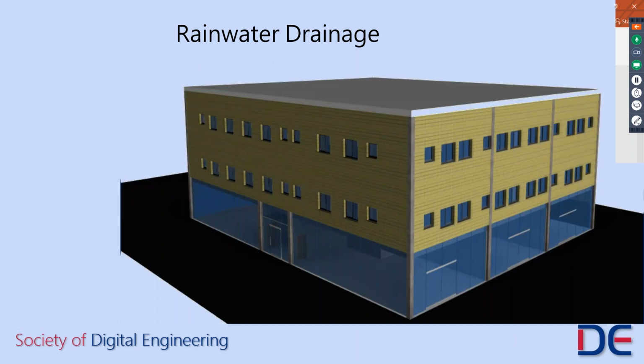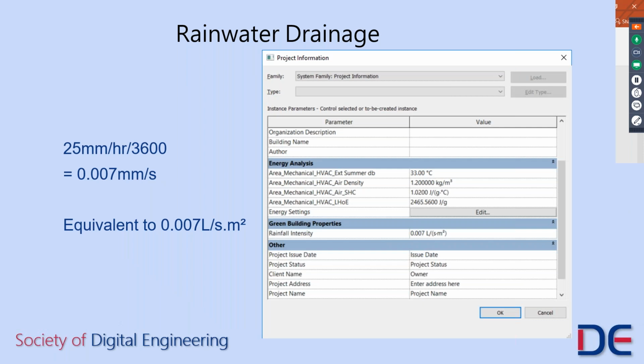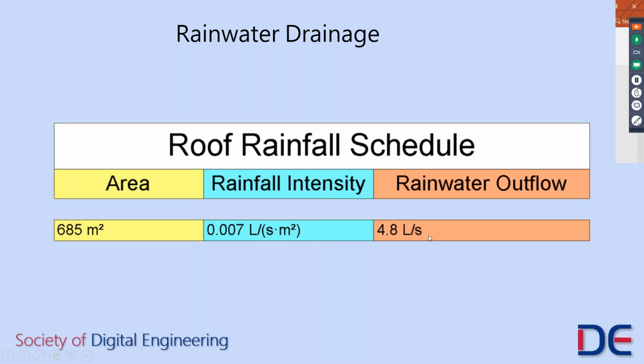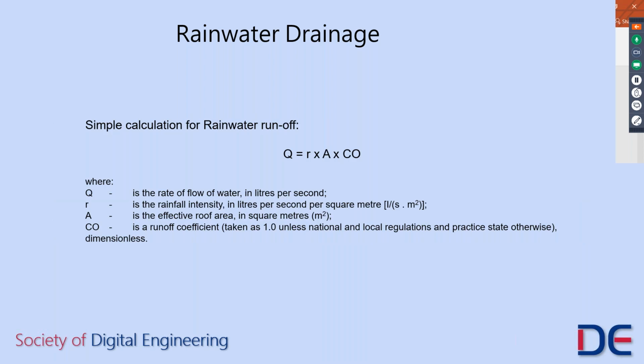Again, we're going to use the building that we created for the earlier mechanical presentation on these automations. Traditionally, the rainfall intensity is given in millimeters per hour. And what we actually want to do the calculation is liters per second per meter squared. And to get one to the other, all we need to do is divide the millimeters per hour by 3,600, which gives us our liters per second per meter squared. And we can then input that as part of the project information. We can then create a very, very simple schedule where what we're measuring is the roof area, which is available through the architectural model, the rainfall intensity, which is our parameter, and that multiplied by other factors can give us our rainwater outflow.